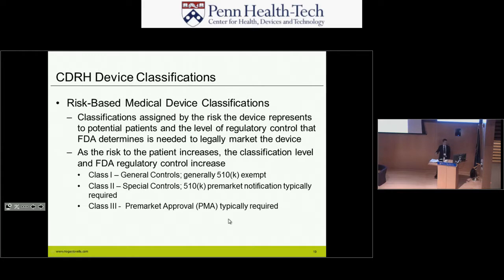So at our baseline level, we have Class 1 devices, which are subject to general controls. Generally, these are what we call 510K exempt devices, meaning that as long as you're applying the general controls that FDA thinks should apply to basically every medical device, you'll be okay. You don't need to submit a 510K notification. But this is very case specific, depending on the types of claims you're making and the types of technology that you're using. And you have to be very careful about whether you fall into this exemption window. And those will all be in your regulations.